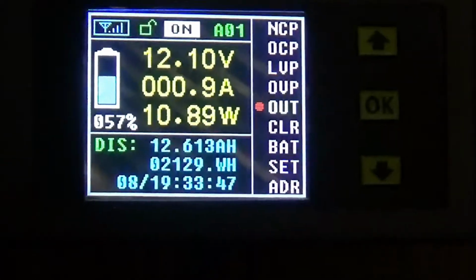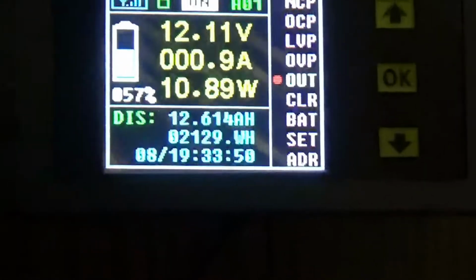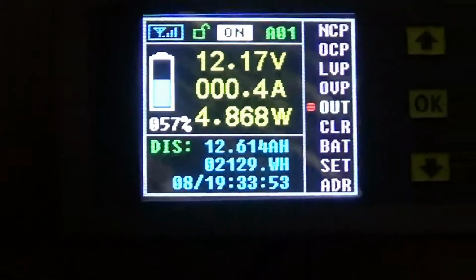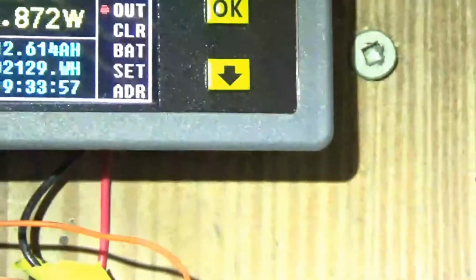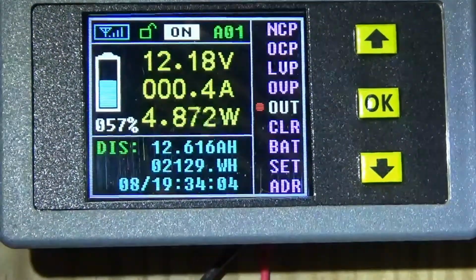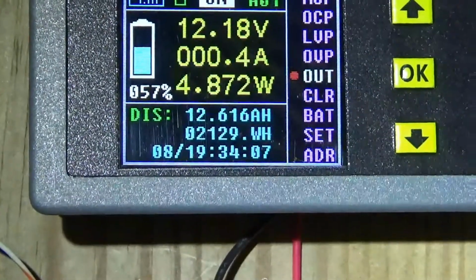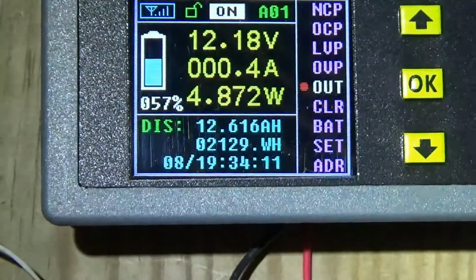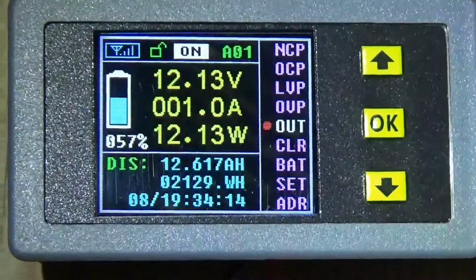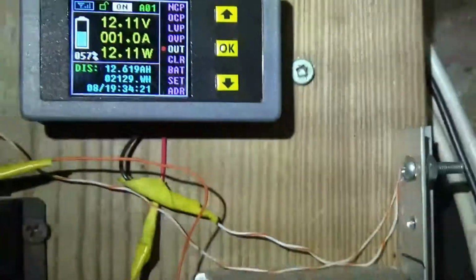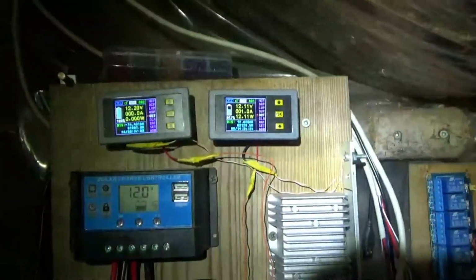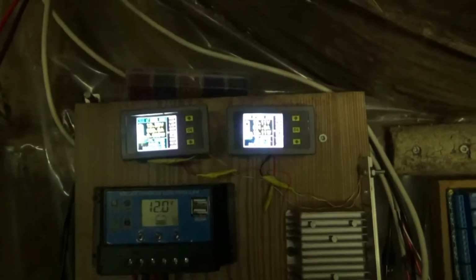I'll give a quick power consumption clip. The pump is running... the pump is off... and I'll put it back on. Sorry for the shaky camera. Off: 4.8 watts with an occasional 6-watt bump, about 4.87 watts. Pump on: 12.12 to 12.8 watts, so that's about 8 watts draw. I was expecting it to be 36, so that's much better, and it means we can move heat very efficiently off solar power.